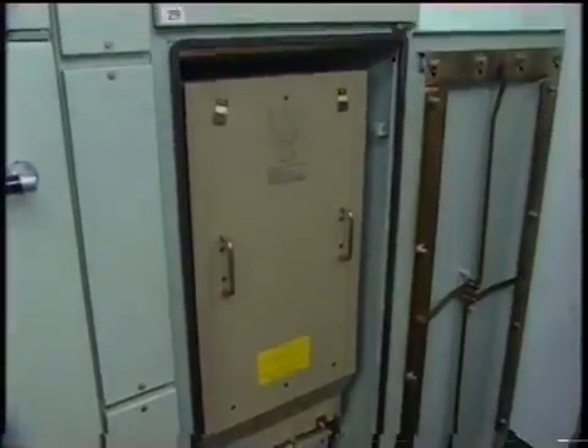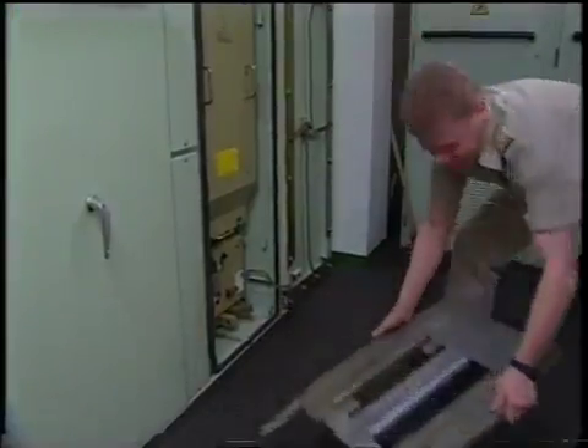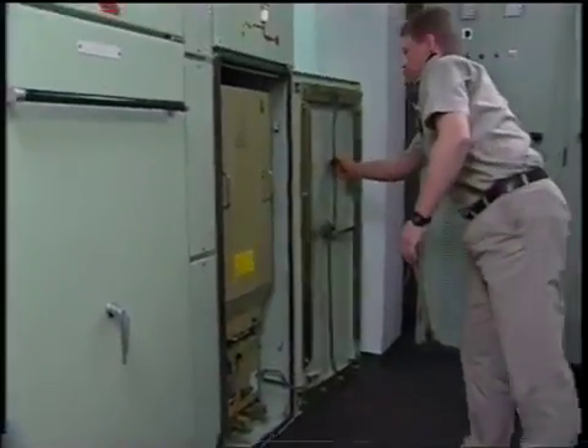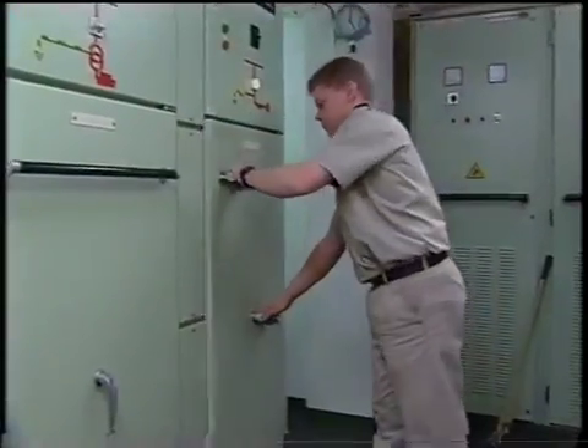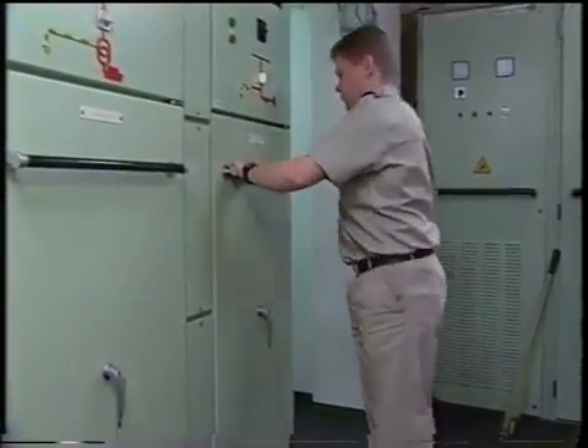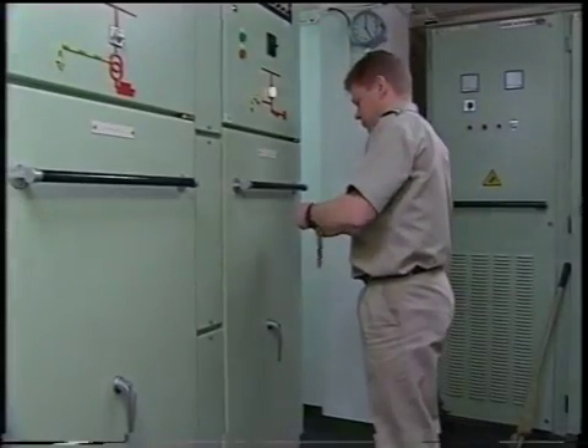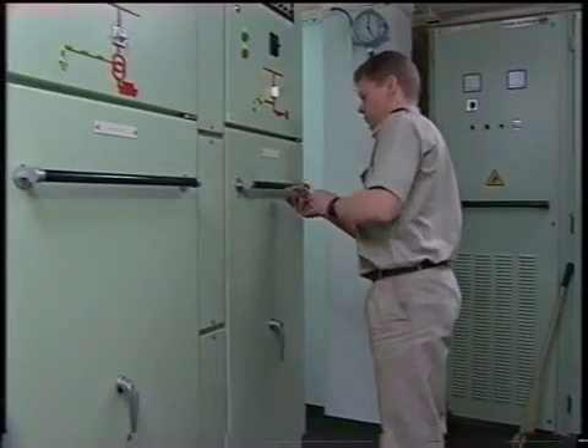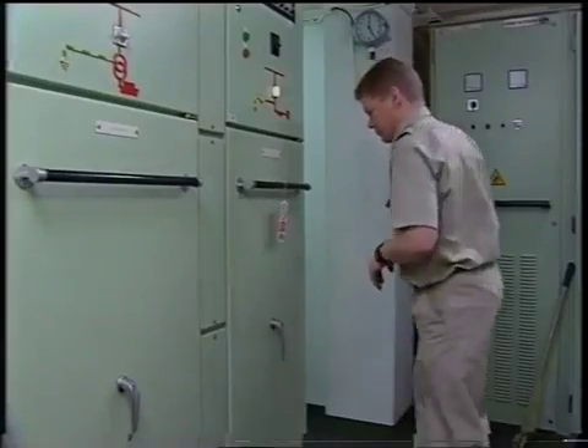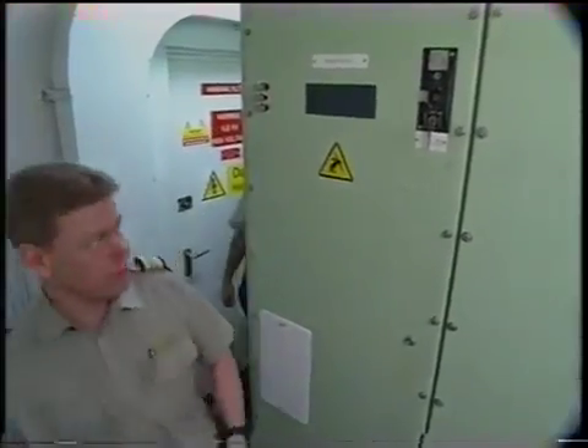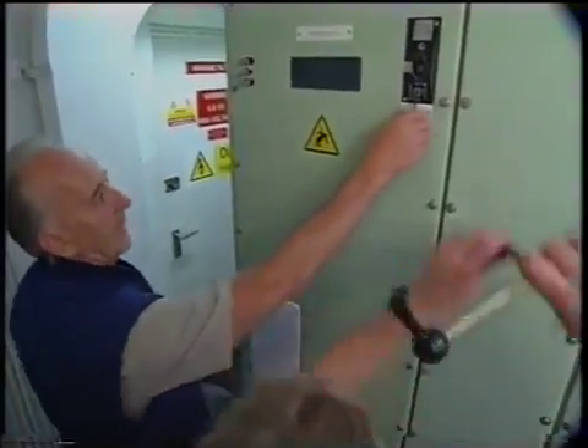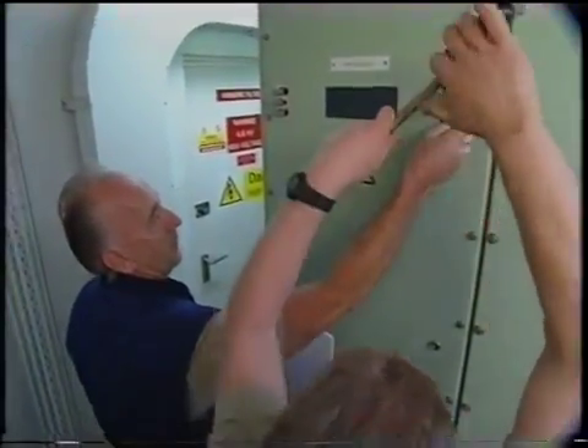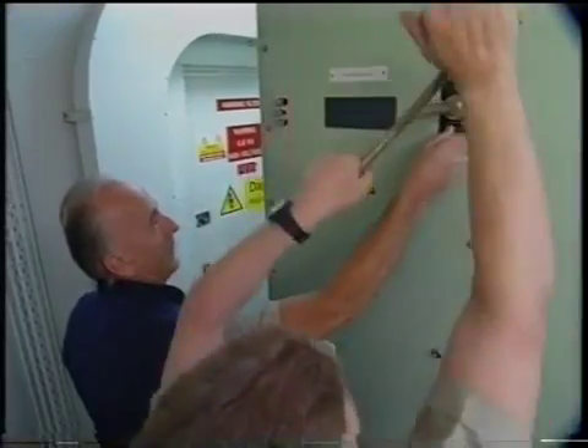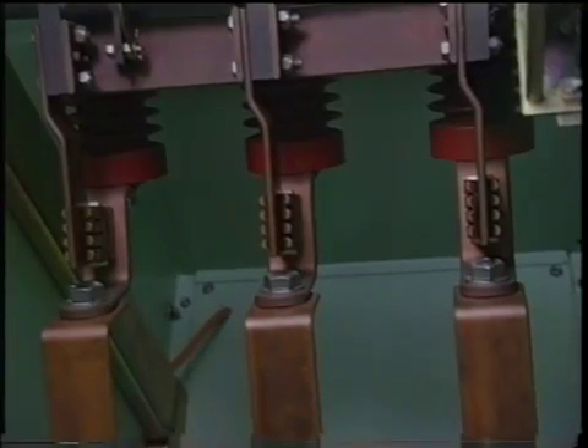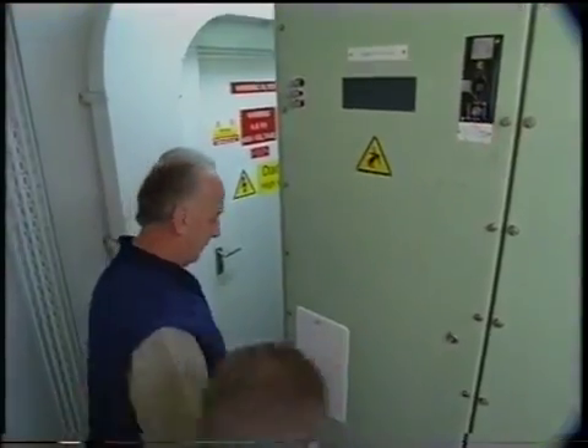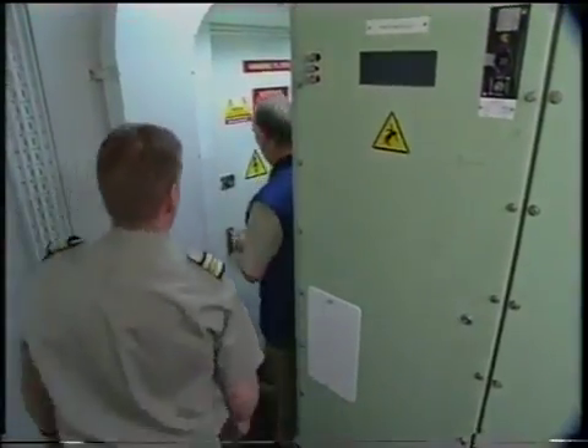Firstly, they disconnect and isolate the relevant breaker. This one is of the standard air brake type. The panel door is closed again, and a safety note is hung in a prominent position. At the back of the cabinet, the cable is connected to earth through an earthing switch. This process releases a trapped interlock key, which is then used to gain entry into the filter room.